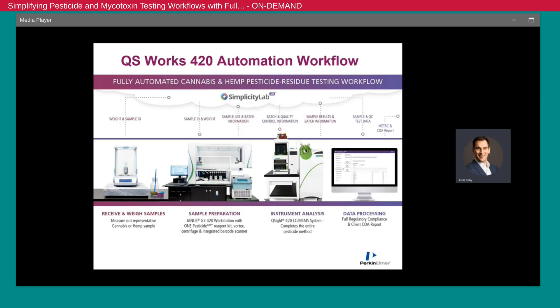What we've been able to develop is a specific workflow called QS Works 420 Automation, which includes the Microbalance, the Janus 420 Sample Preparation Platform, the QSight 420 LC-MS/MS, and finally Simplicity Lab 420 — a cloud-based software that communicates and transports data across the entire workflow, presenting it in a certificate of analysis or even to a METRC in the compliance environment if needed.